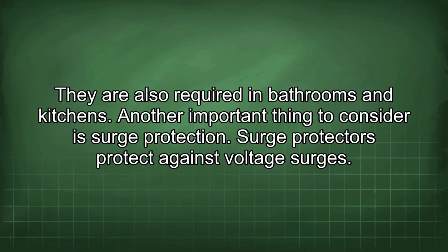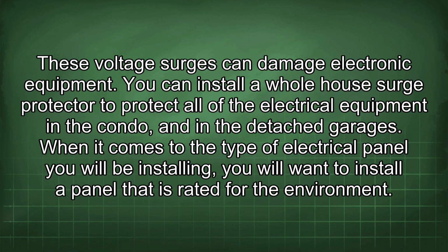Another important thing to consider is surge protection. Surge protectors protect against voltage surges. These voltage surges can damage electronic equipment. You can install a whole house surge protector to protect all of the electrical equipment in the condo and in the detached garages.